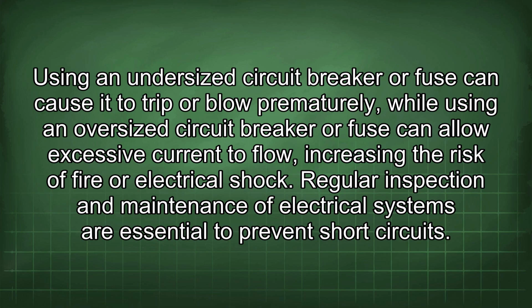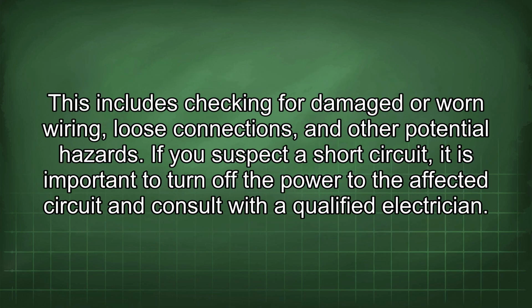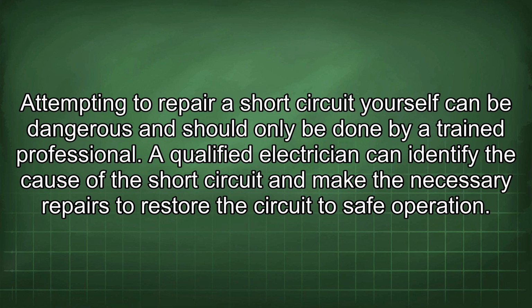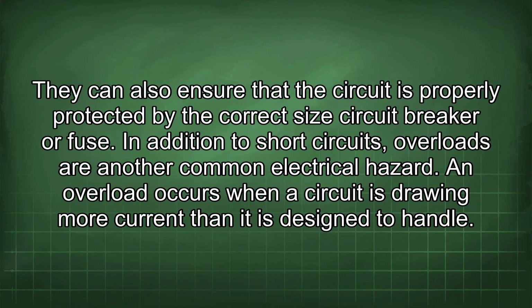Regular inspection and maintenance of electrical systems are essential to prevent short circuits. This includes checking for damaged or worn wiring, loose connections, and other potential hazards. If you suspect a short circuit, it is important to turn off the power to the affected circuit and consult with a qualified electrician. Attempting to repair a short circuit yourself can be dangerous and should only be done by a trained professional. A qualified electrician can identify the cause of the short circuit and make the necessary repairs to restore the circuit to safe operation. They can also ensure that the circuit is properly protected by the correct size circuit breaker or fuse.